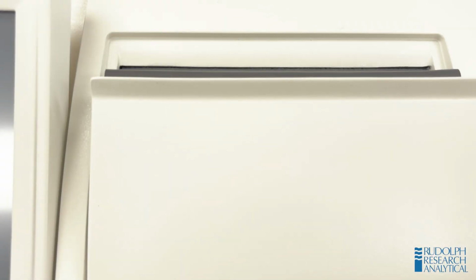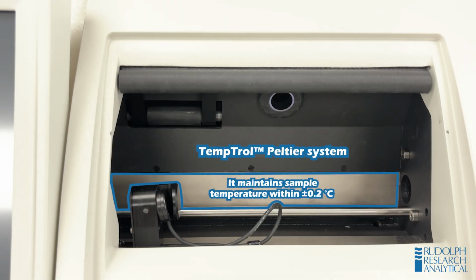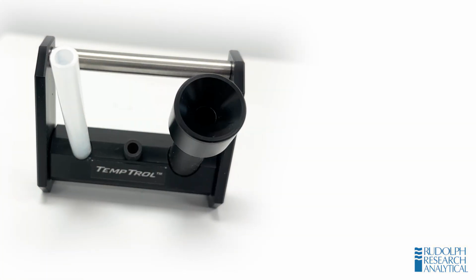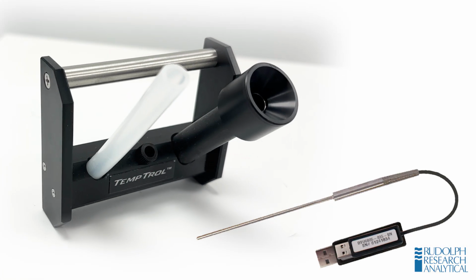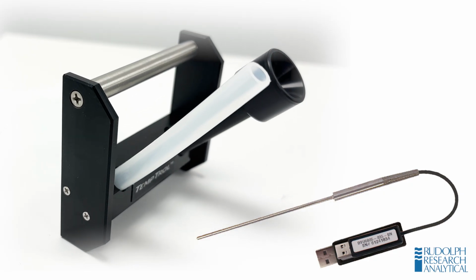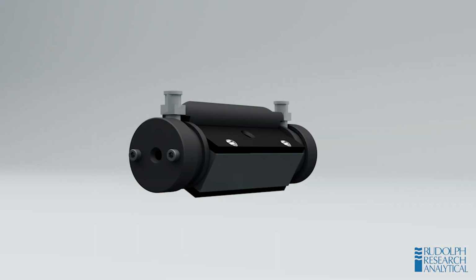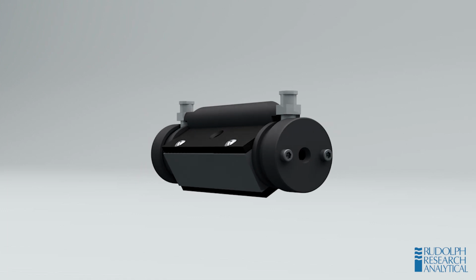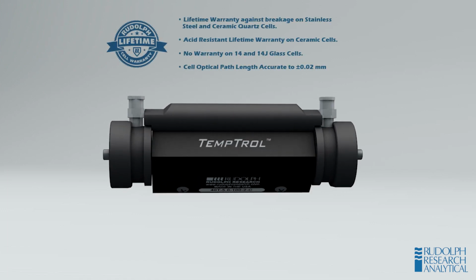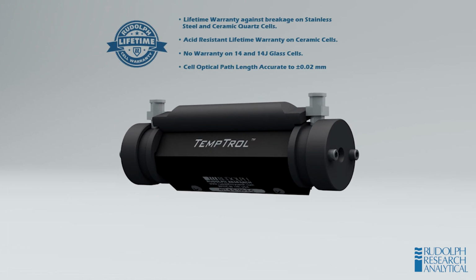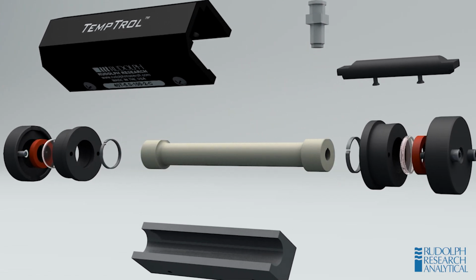Temperature stability is managed by Rudolph's patented TempTrol Peltier system. It maintains sample temperature within ±0.2 degrees Celsius and automatically links the temperature reading to each analytical measurement. Validation cells and NIST traceable thermoprobes are available to confirm performance and maintain audit-ready documentation. Rudolph ceramic quartz sample cells come with a lifetime warranty against breakage or acid corrosion. Measurement chambers are coated for long-term resistance to chemical attack. These features ensure durability and low maintenance under even the toughest lab conditions.